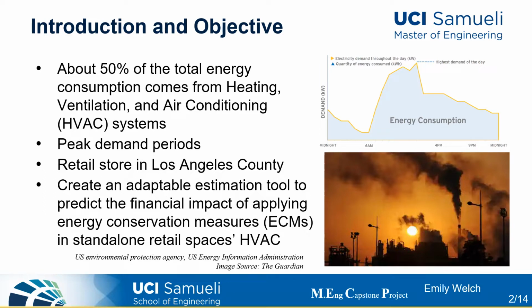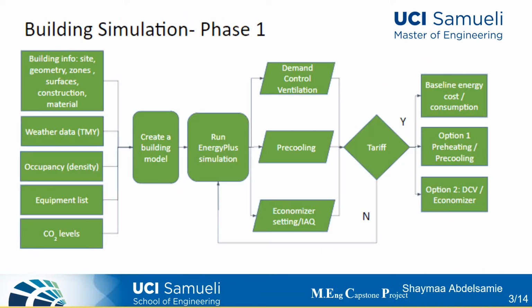We've created a tool that will estimate from these optimized set points the energy and financial savings for a retail space in Los Angeles County that can be adapted for other locations. HVAC conventional control logic only considers static parameters like indoor temperature and air quality. Our team is building an autonomous, artificial intelligence-based system that optimizes a building's HVAC set point every 15 minutes by evaluating dynamic parameters such as weather, time of day, occupancy. Our solution is expected to deliver significant energy savings while decreasing a building's carbon footprint.